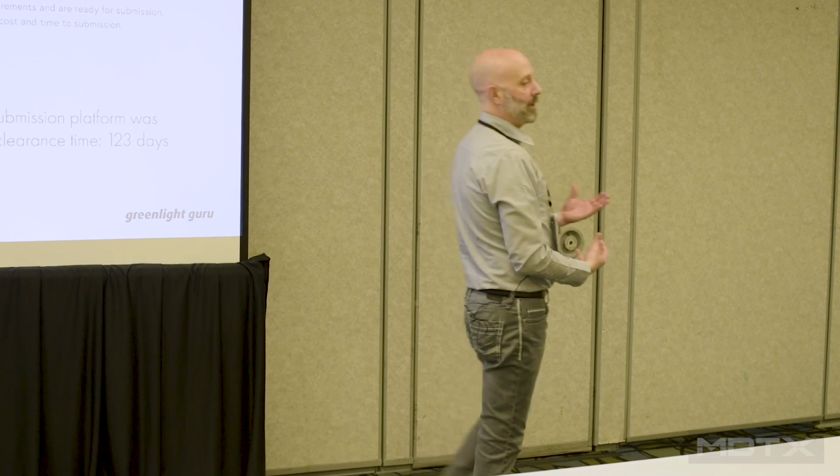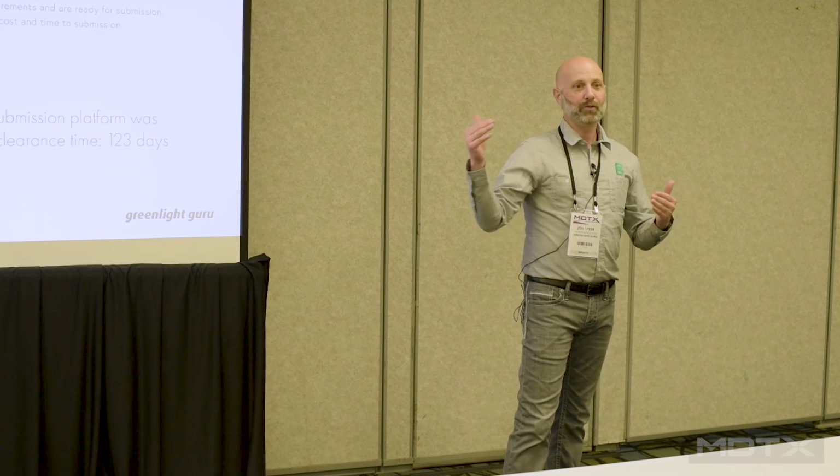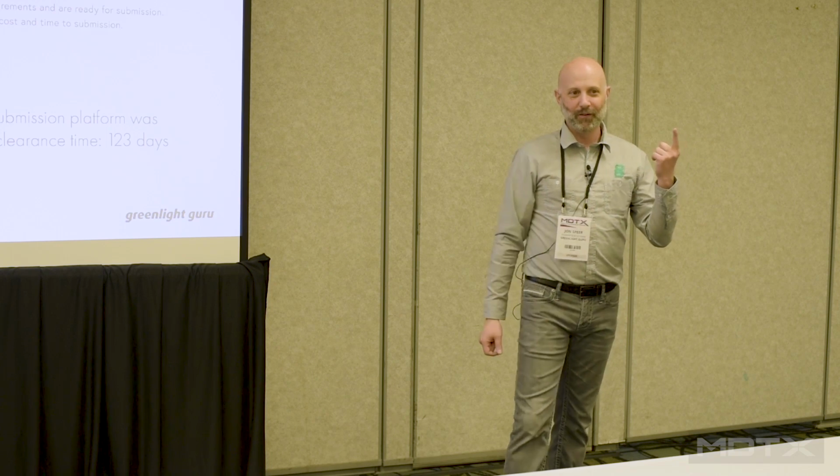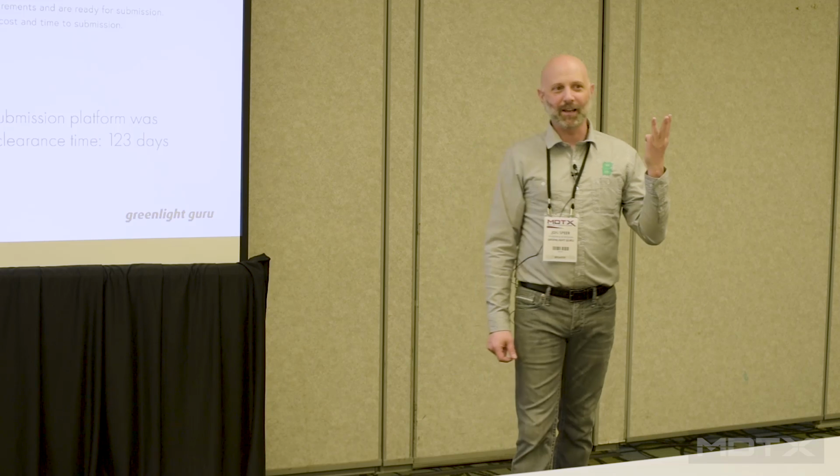And then as you progress toward your submission, there may be other parts and pieces that are appropriate. There may be some things that you need to do from a manufacturing standpoint and so on. So you may start to turn on other parts and pieces of your quality system. Then you submit your 510K, and now you can finalize the rest of that quality system so that by the time you get the clearance letter, you build it as you go, build it as you need. Can you say those for me? Design control, risk management, supplier management, document management. At a bare minimum.